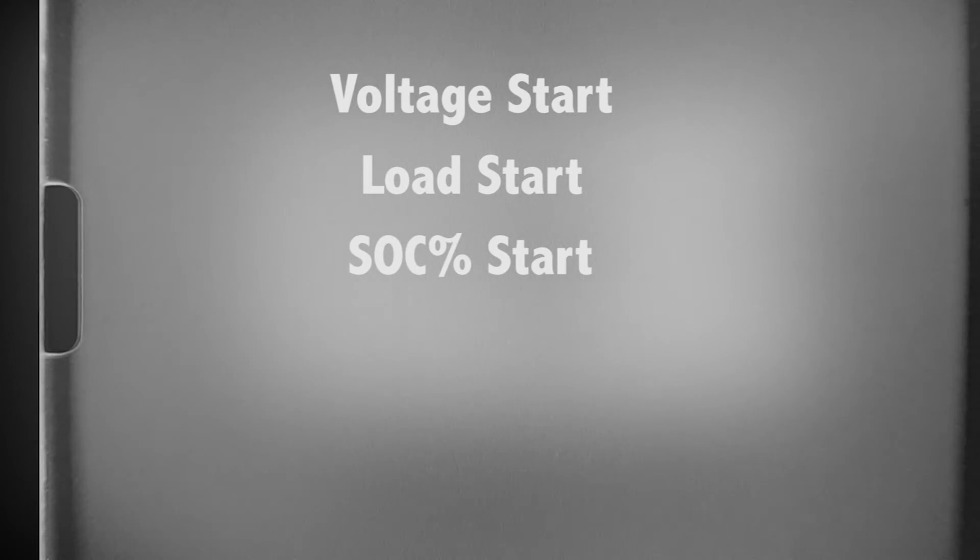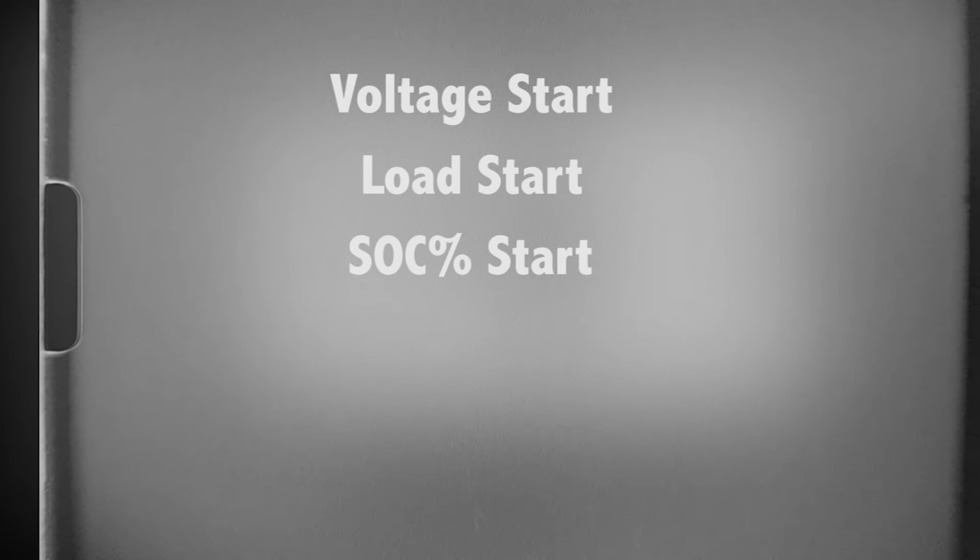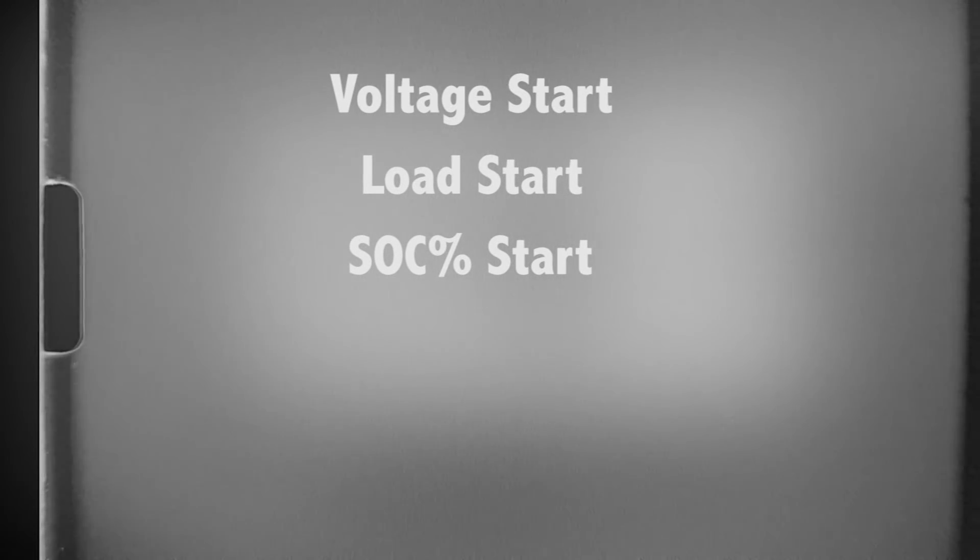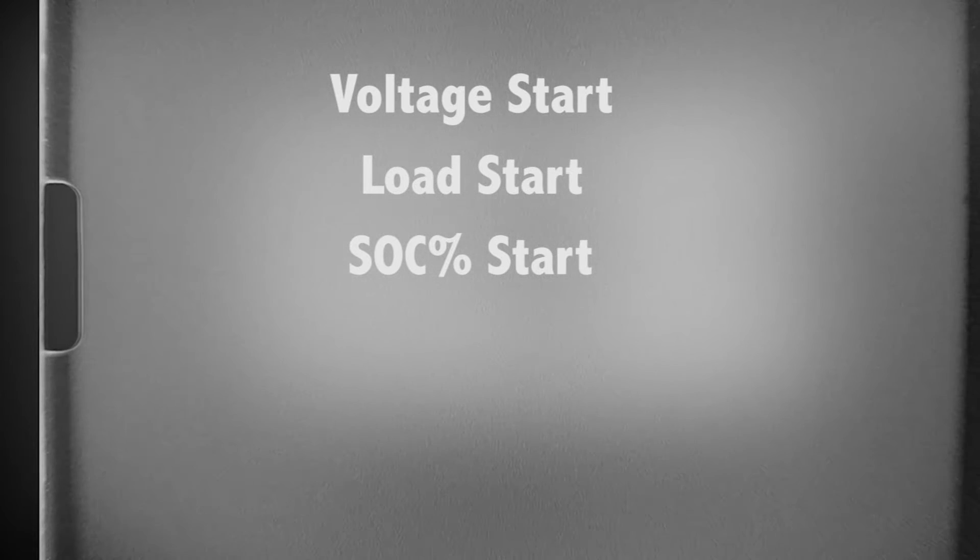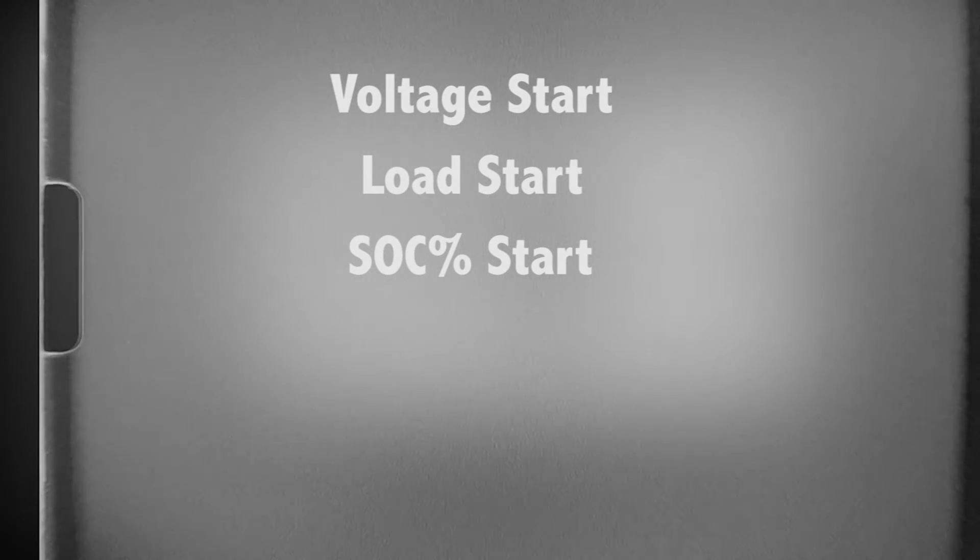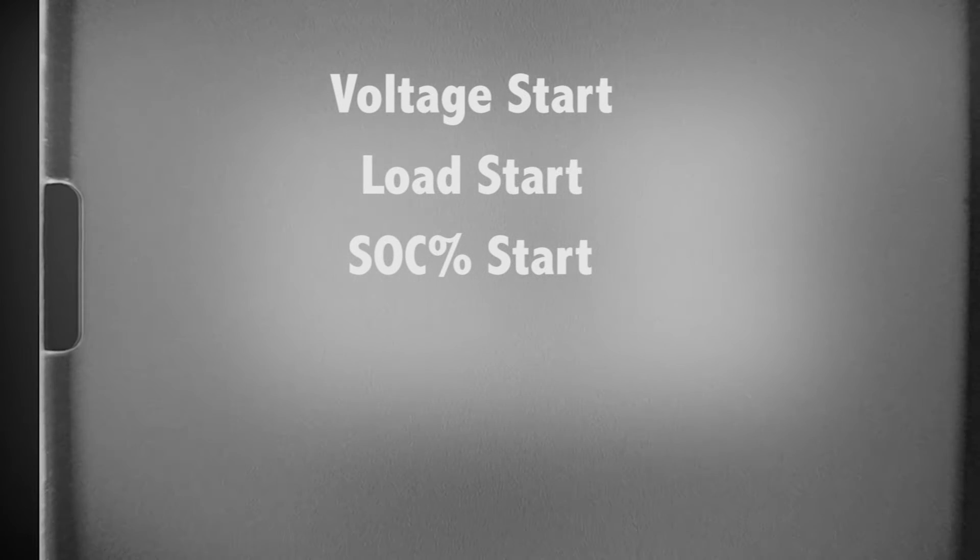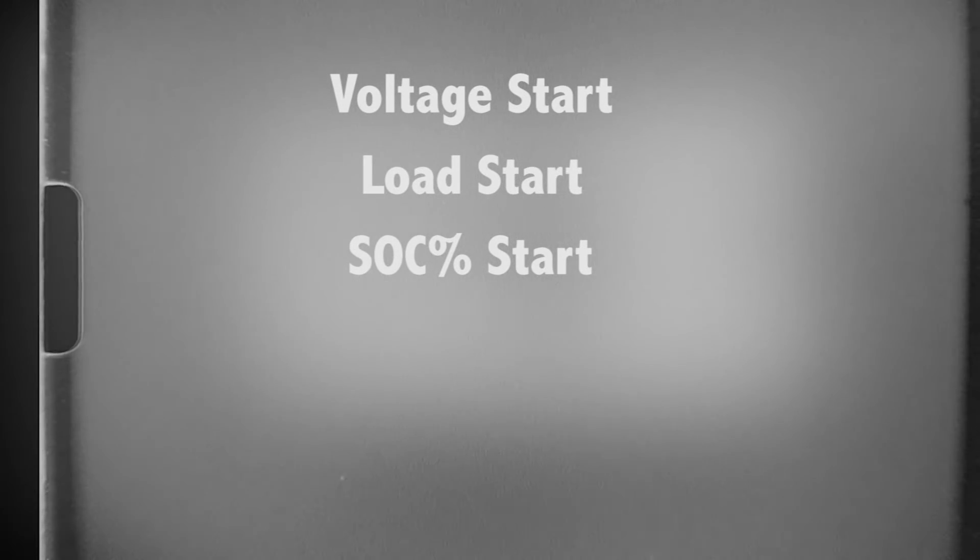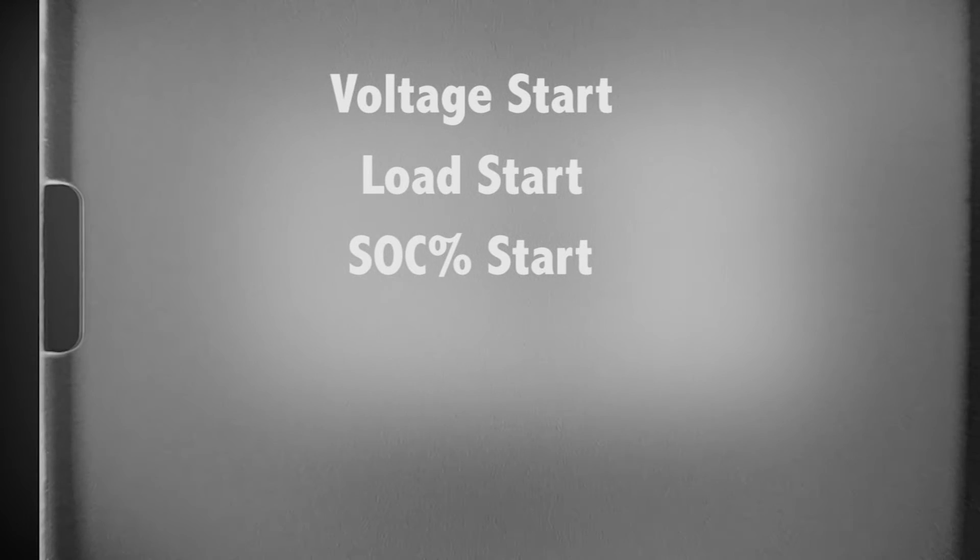State of charge percentage start. This start condition only works when a FlexNet DC is present. The generator can be started based on the battery state of charge rather than the voltage. Note, this feature may become less accurate if the system routinely cycles without obtaining a full charge for long periods of time.